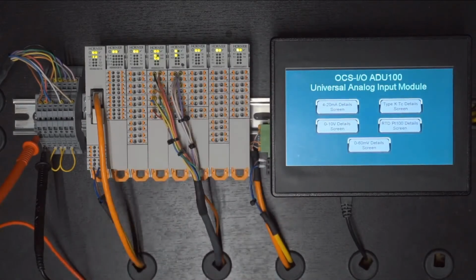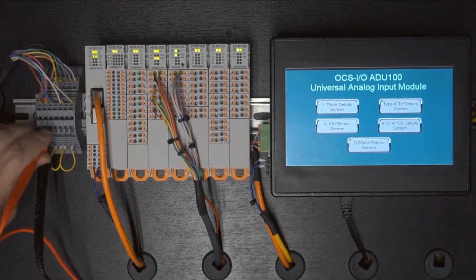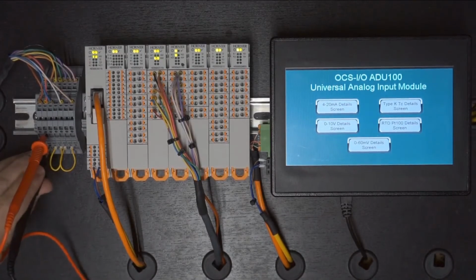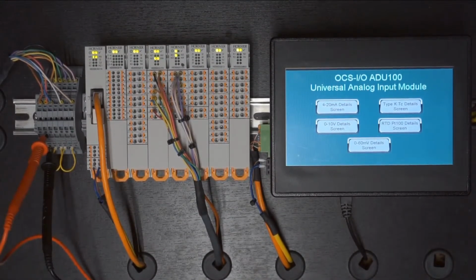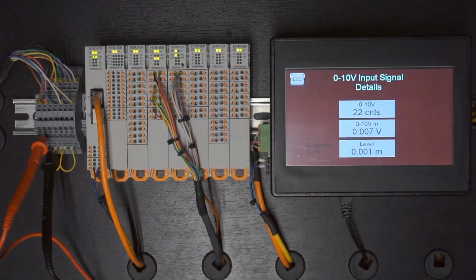All right, so now we need to switch to voltage range to show you voltage range. I've got to move my probes from the milliamp position to the voltage position, which I'm doing off camera here. All right, yep, they're definitely in there good and tight. Then I need to move the output of my simulator to the next voltage channel. And let me change my simulator configuration from milliamp to voltage, which I've done now. Let's go to, say, a mid-level range of 5 volts. And then let's take a look here.